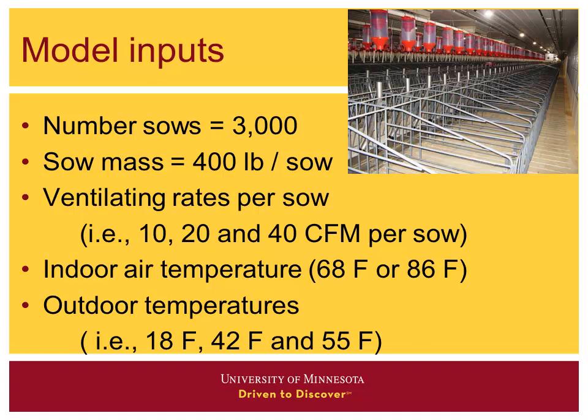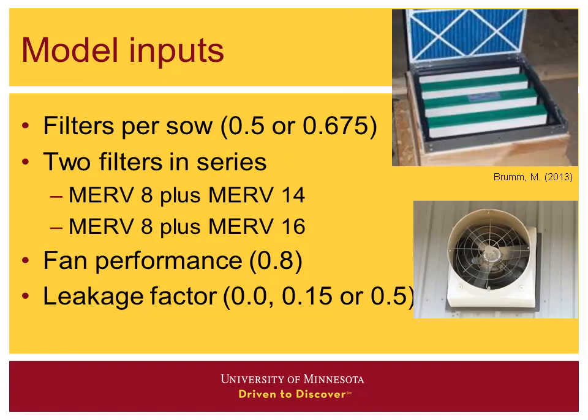We used a 3,000-sow barn because that's one of the data sets we had. We assumed 400 pounds per sow. Ventilating rates of 10, 20, and 40 CFM per sow. Interior temperatures of either 68 or 86°F, corresponding to outside temperatures of 18, 42, and 55°F. Filters per sow from industry input: half a square foot, or half a filter per sow, or 0.675. We had two filter series: MERV 8 plus MERV 14, and MERV 8 plus MERV 16.